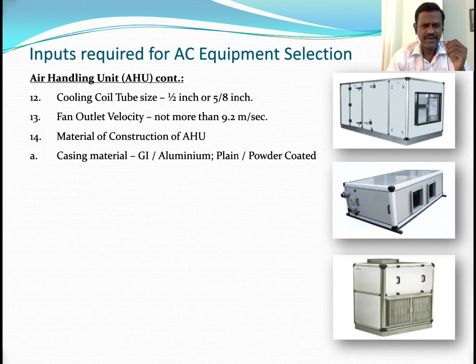Then material of construction of the AHU: the casing material is either GI or aluminum. Then you want plain or powder coated. Framework extruded aluminum. Insulation material, whether it is going to be PUF or rock wool. Then thickness you have to specify, whether you want 25 mm or 50 mm. Cooling coil tube and fin material you have to specify. Coil drain pan shall be made out of SS304 and it should be insulated with minimum 10 mm thick insulation.